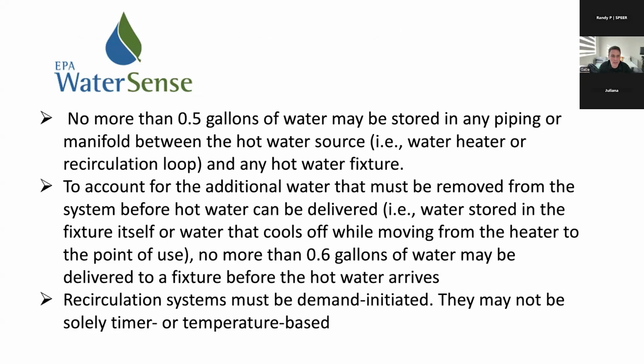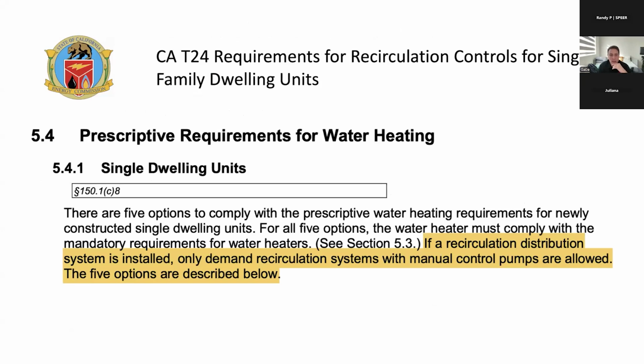And then WaterSense is very similar to LEED and the DOE's requirements as far as recirculation on demand. In California, we have what's called Title 24, and their requirements are that in new construction, if you're doing a recirc pump, it must be demand controlled with manual switches. You can use the option of occupancy sensors, but there is a slight energy penalty. They calculate that, with an occupancy sensor, from time to time you'll get a false signal for demand and the pump will prime the loop. But the energy penalty is not anything too severe.